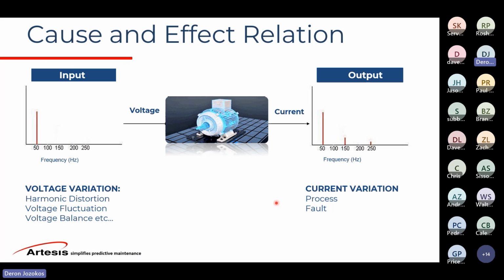So it's truly a cause and effect relationship. Since we're monitoring those voltage distortions, those can also affect your motor health. So we track and trend and report any anomalies or anything that breaks a threshold, those THD, total harmonic distortions, and the odd harmonics that can deteriorate your motor, the windings, rotor, stator issues, insulation. So those are also tracked and trended. We're also going to track and trend all the voltage and current fluctuations, voltage and current balances. And we're going to talk about how it learns, and gets these process-related faults as well.